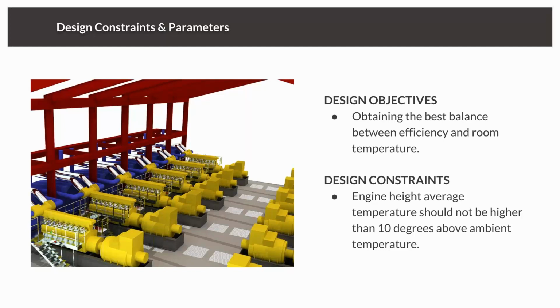Our objective is to find the best balance between the efficiency of the performance for the room, so the lowest temperature in the room, while keeping the lowest possible volume flow rate and maintaining the temperature in the vicinity of the engine not higher than 10 degrees above the ambient temperature.